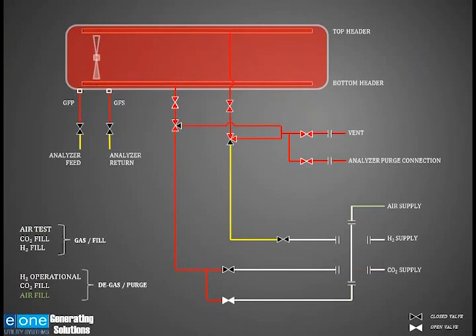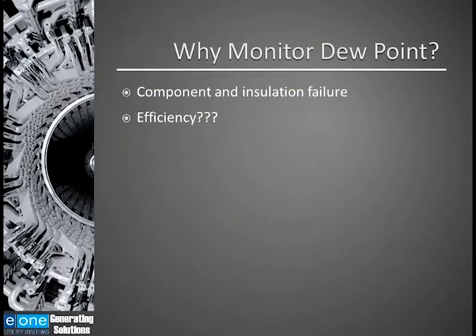Now I'm going to talk about measuring dew point. Why do we measure dew point? The main reason is to prevent component failure and insulation failure, and for risk mitigation. Whether dew point affects efficiency is often debated, and I will show a slide later in this presentation that supports the fact that dew point has very little effect on efficiency. I don't think there are any safety issues related to having high dew point, although if a retaining ring lets go, I guess you could have a safety issue.